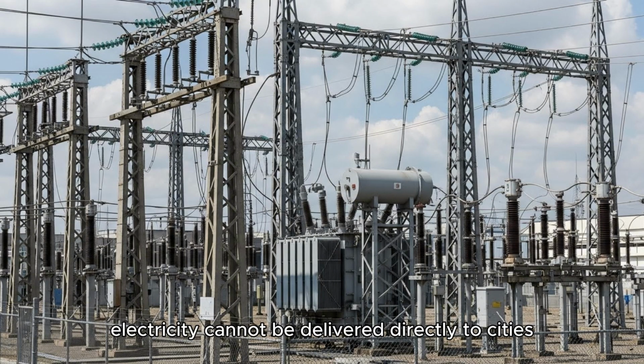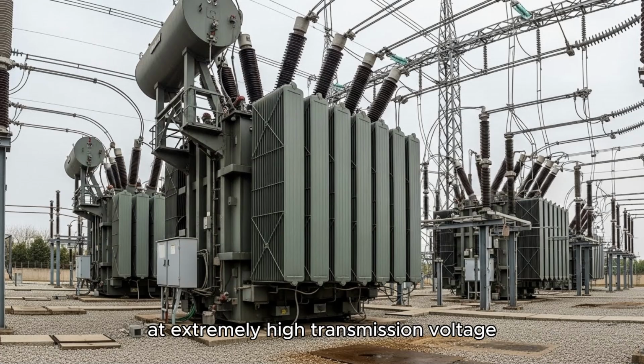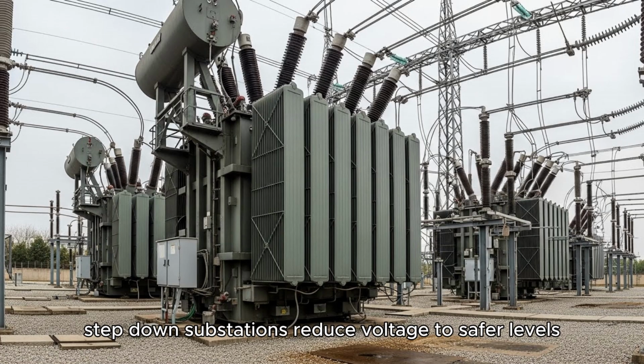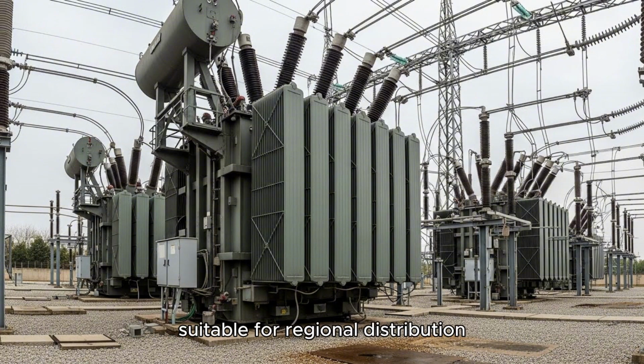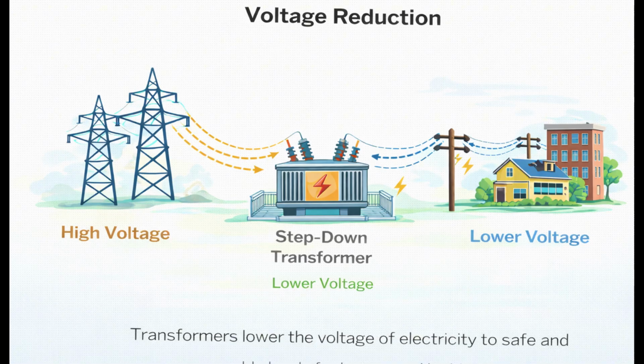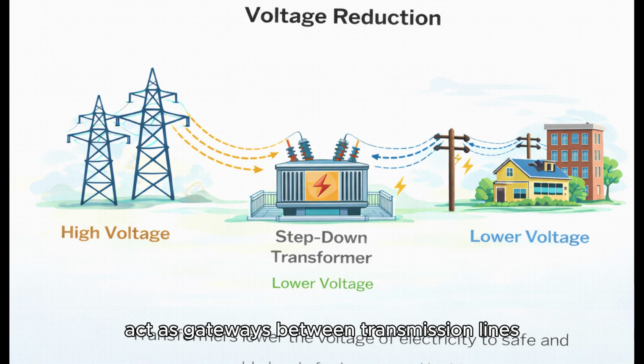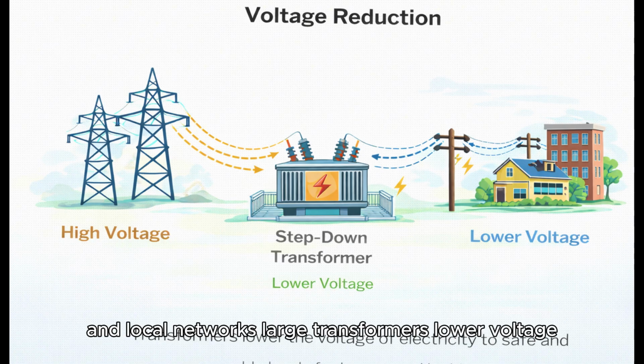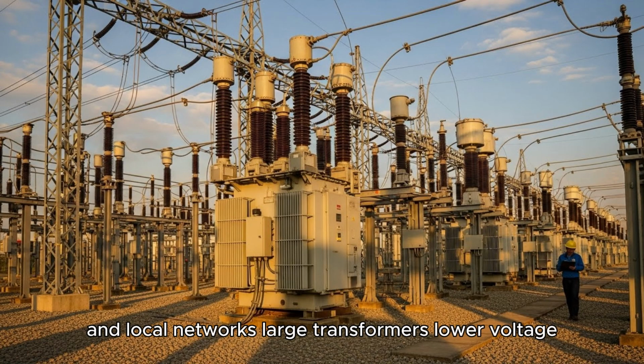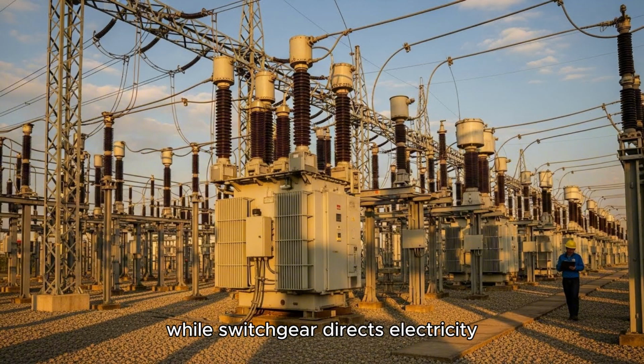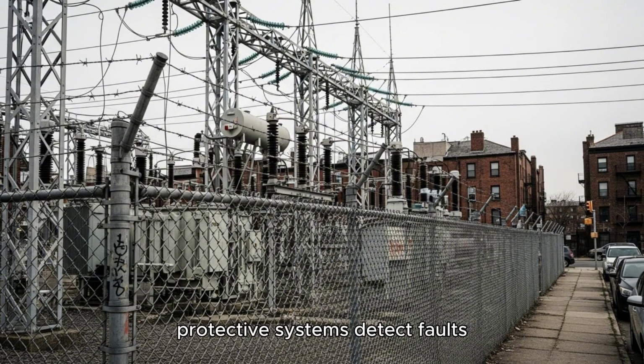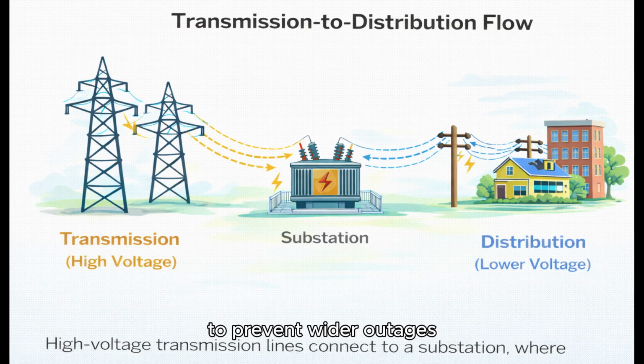Electricity cannot be delivered directly to cities at extremely high transmission voltage. Step-down substations reduce voltage to safer levels, suitable for regional distribution. These substations act as gateways between transmission lines and local networks. Large transformers lower voltage, while switchgear directs electricity along different routes. Protective systems detect faults and automatically isolate damaged sections to prevent wider outages.